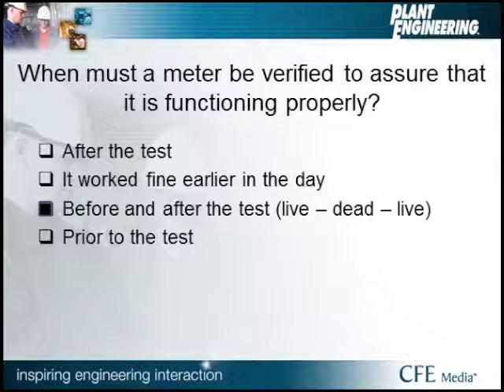When must a meter be verified to assure that it's functioning properly? And that's before and after every test, what we call the live, dead, live testing.